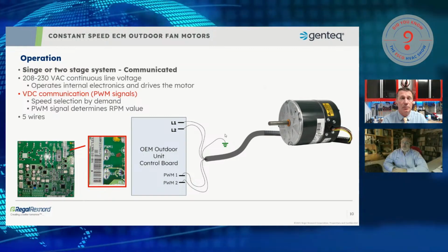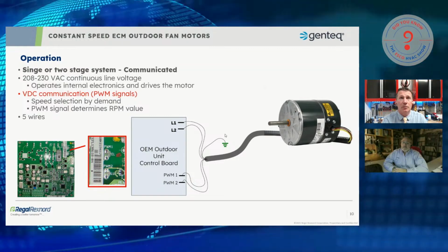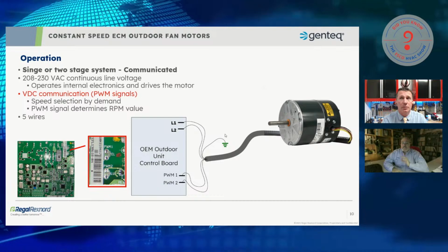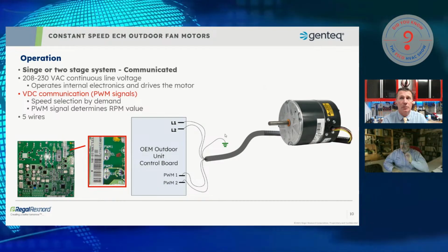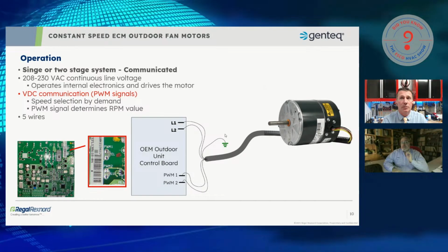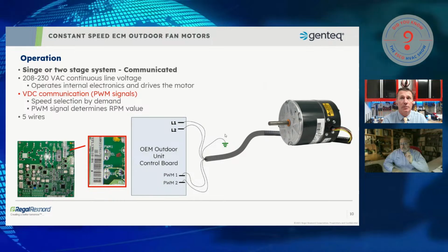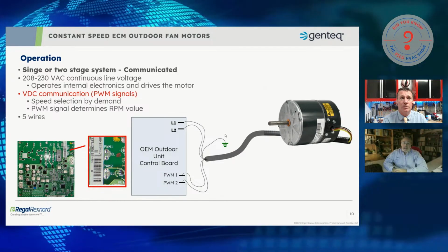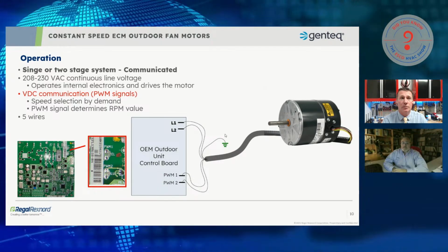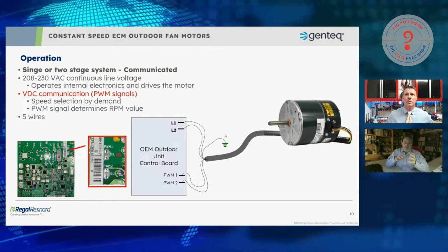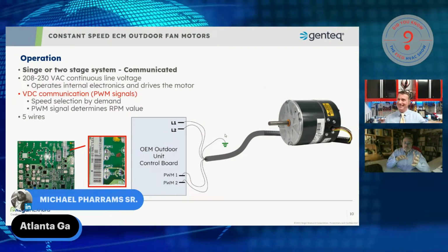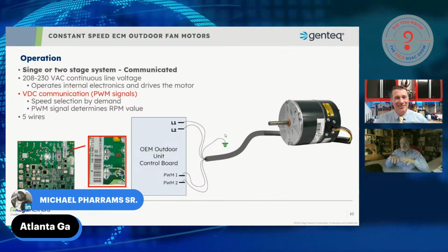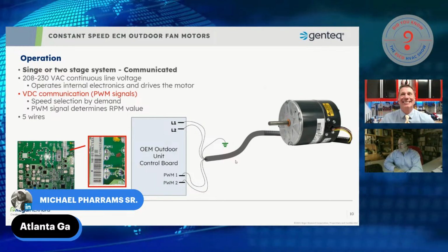The PWM signal determines the RPM. So not only is the volts DC, the PWM signal, the on command for the motor, but the value of that signal, the value of that DC voltage, actually determines how much RPM the motor is going to run at. Higher voltage, higher PWM signal, the motor's going to run faster. Lower voltage, lower signal, the motor's going to run slower.